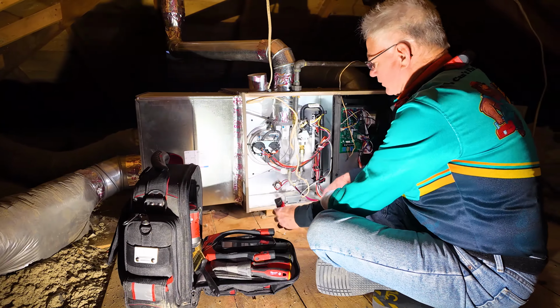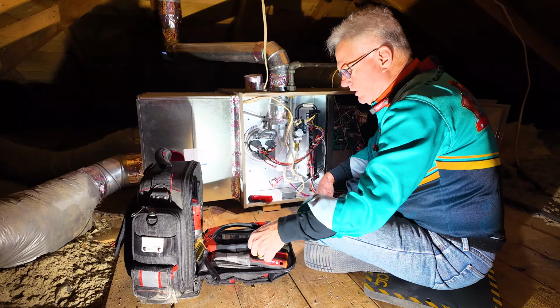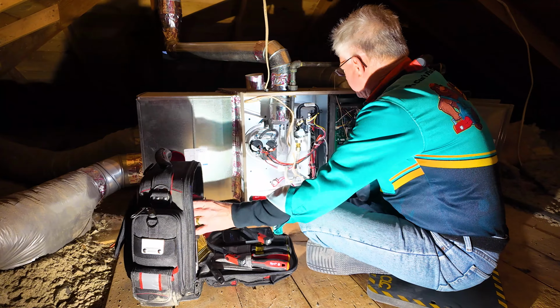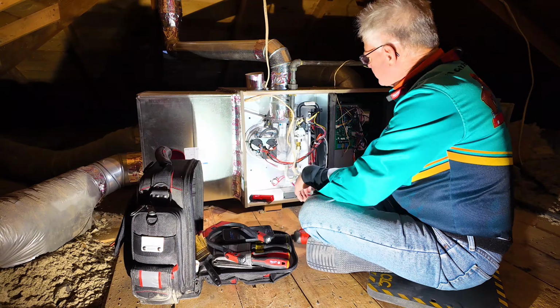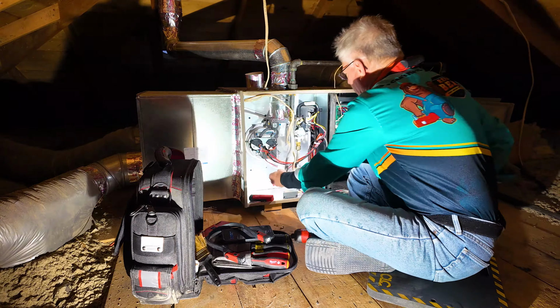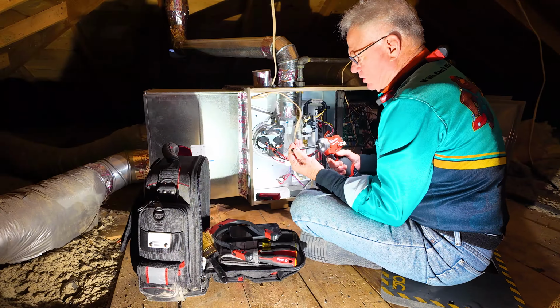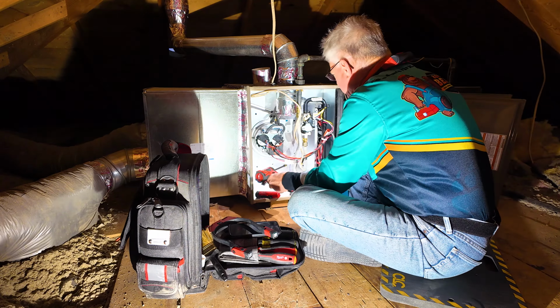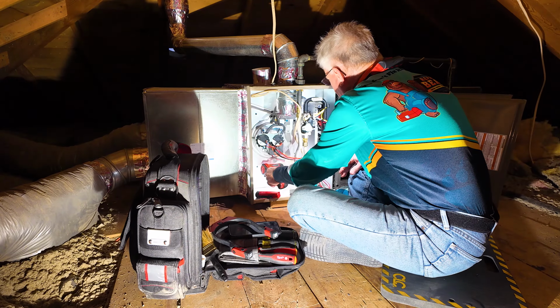So while it's still cool, before I crank it up and run a cycle on it, because it did run, it did come on, the first thing I'm going to do is go ahead and just remove that flame sensor. I'll do that by just pulling this wire off of it back here. It's 25 degrees outside, so I'm glad that it's an inside job here this morning. Okay, so I'm going to take off this flame sensor rod and pull it out, and then we'll look at it.